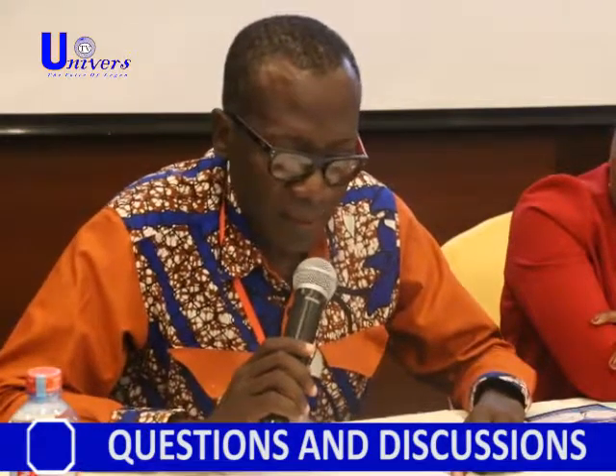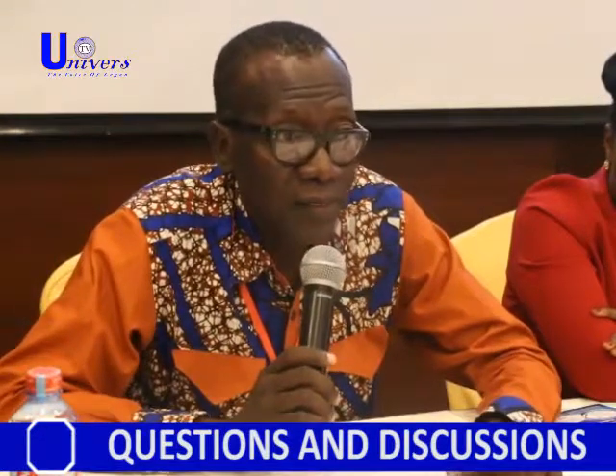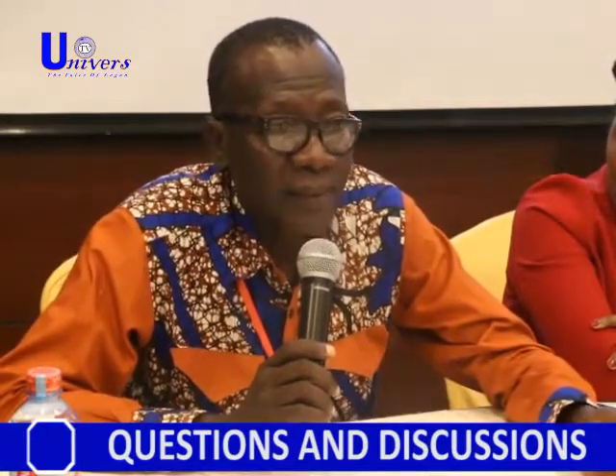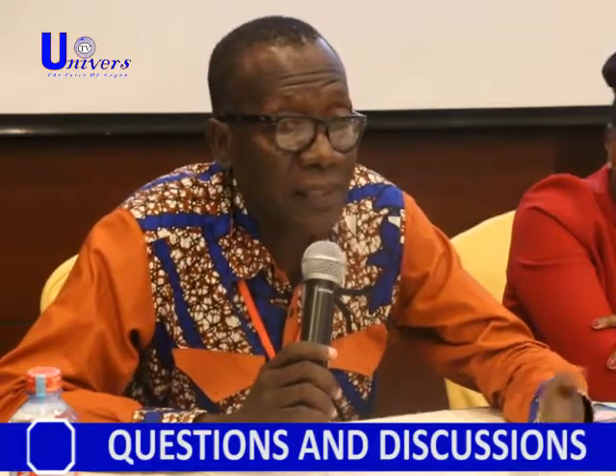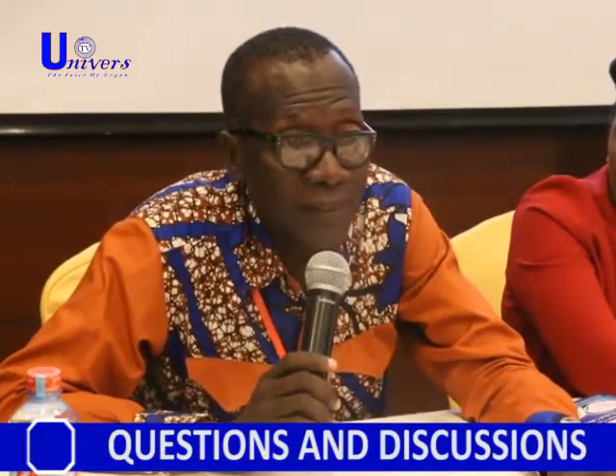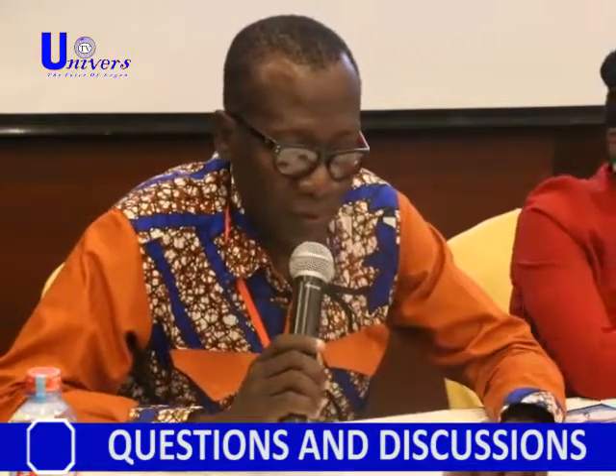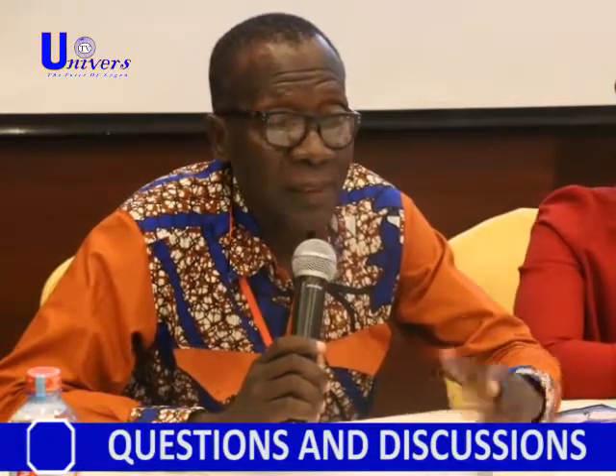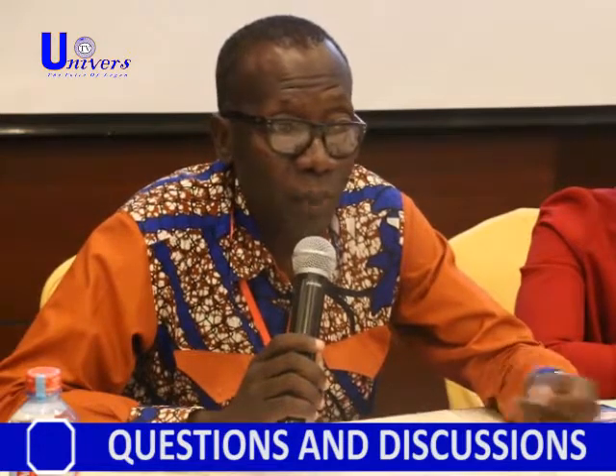And two, the question is, what is calibration? Calibration, in simple language, is comparing the readings of a standard instrument which we keep for the country with the instrument that the medical facility has submitted to us. So if the difference in readings is too high, then we'll have to alert you that the equipment is no longer useful for the purpose. So basically, it's a comparison process. We use the national standard to compare with the readings of the instrument you have submitted to us.